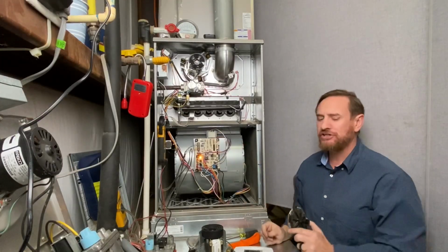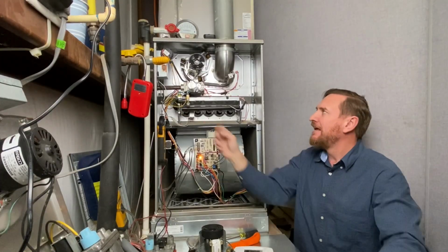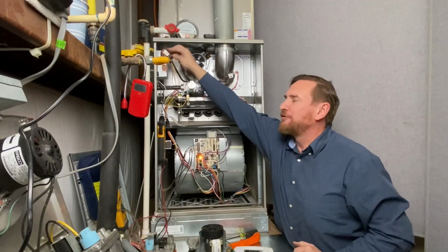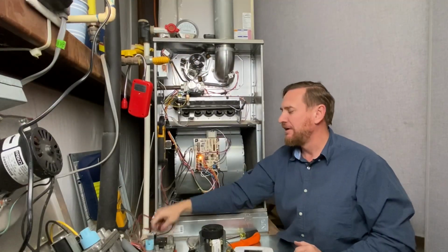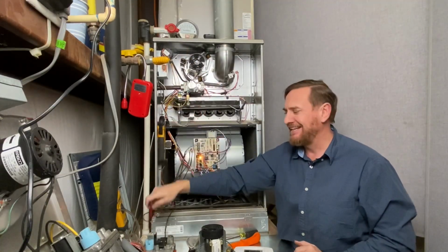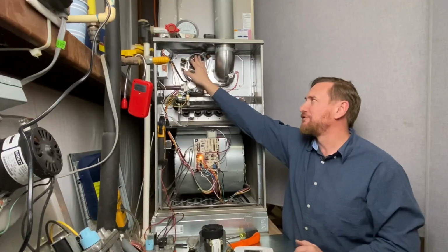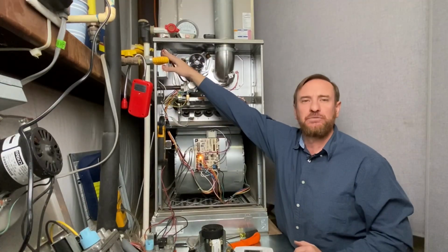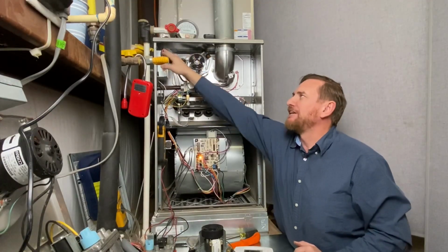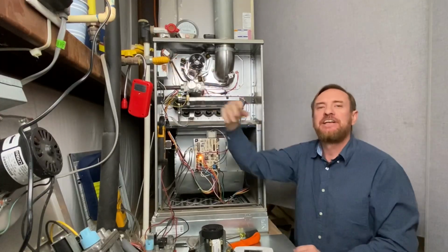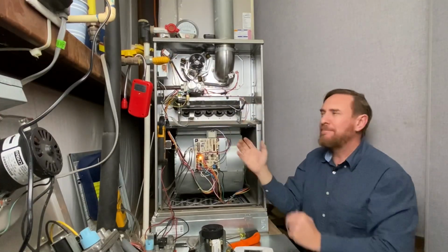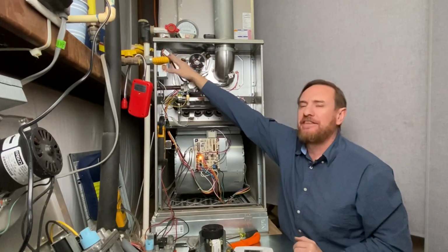Another thing that we can do to check to see if that switch is closing is we can pull these wires back just a little bit. We can use our meter and we can check for voltage. If this motor's running and we're getting 0 volts across there, the switch is closed. If this motor's running and we're getting 24 volts across there, that switch is open. So a lot's happening just between this motor running and this switch closing.